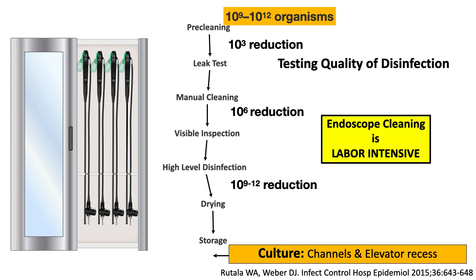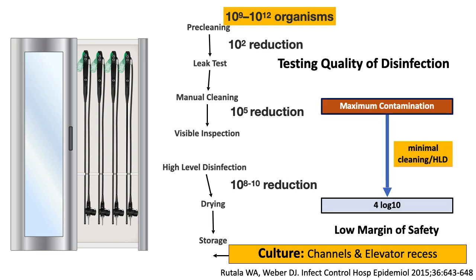So, in summary, as you can see here, once the scope comes out of the patient, it may have 10 to the power of 9 to 12 organisms, and with the pre-cleaning, there is a 10 to the power of 3 reduction, and manual cleaning, 10 to the power of 6 reduction, and high-level disinfection, anywhere between 10 to the power of 9 to 12. All right. So this is a very labor-intensive process. So people can get tired of cleaning the scopes, and if they have a problem, then the scope can get contaminated. Say, for example, if there's maximum contamination of the scope and minimal cleaning that goes on, that results in at least 1,000 to 10,000 microbes per ml remaining. So there is a low margin of safety if the protocol is not adhered to properly.